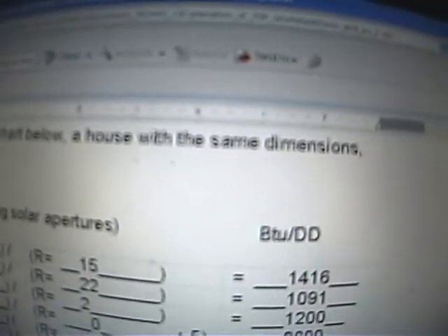That's the heat loss. And it shows you how to calculate the heat loss of the walls, the roof, the east, west, and north windows, the perimeter of the slab. Most of the heat loss out of a slab goes out the edge. Out the basement, out the floor, if you have a crawl space, and then the heat loss due to air infiltration. So, you will notice on that worksheet that there are some similar items to what we learned when we learned the basic air infiltration and heat loss calculations from conduction.